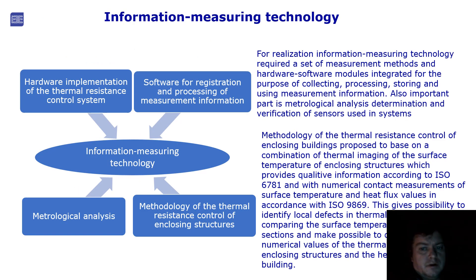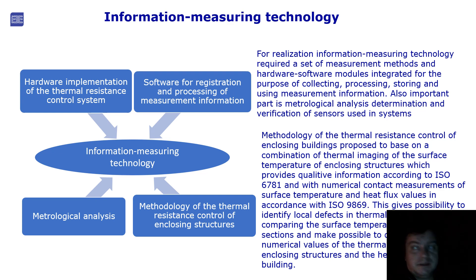The methodology of thermal resistance control is based on a combination of two methods: thermal imaging qualitative method based on standard ISO 6781, and numerical contact measurements method based on standard ISO 9869. This gives us the possibility to provide control of both qualitative and quantitative characteristics of enclosure structures and give recommendations about thermomodernization of enclosure structures.